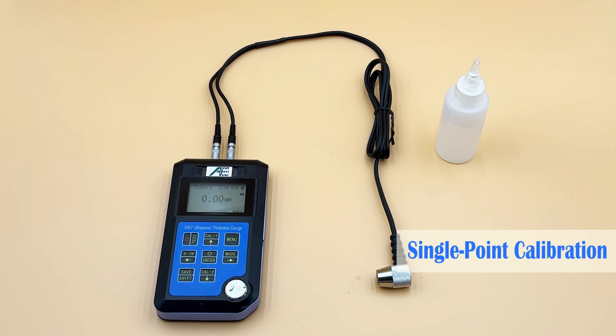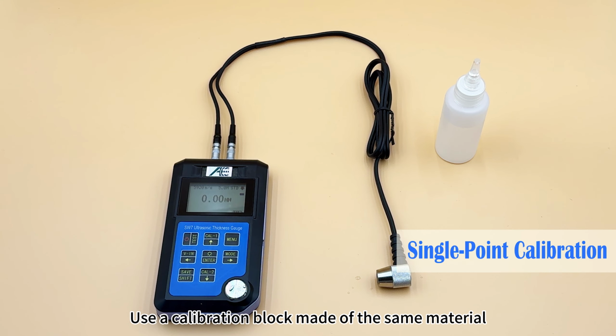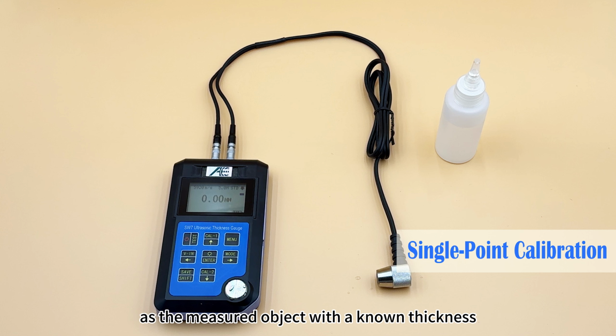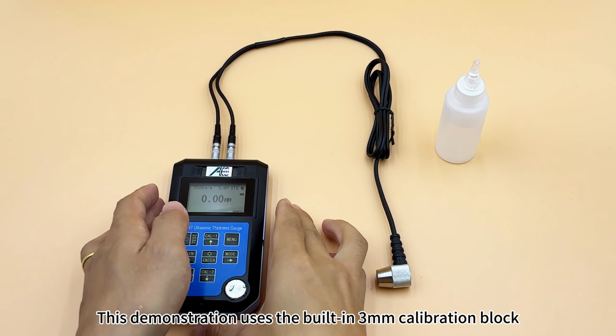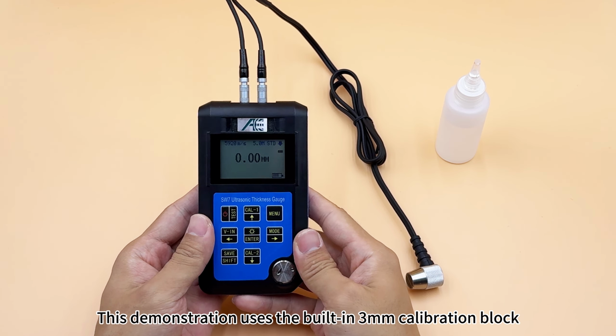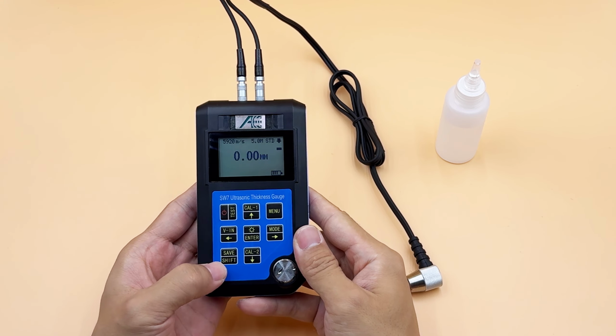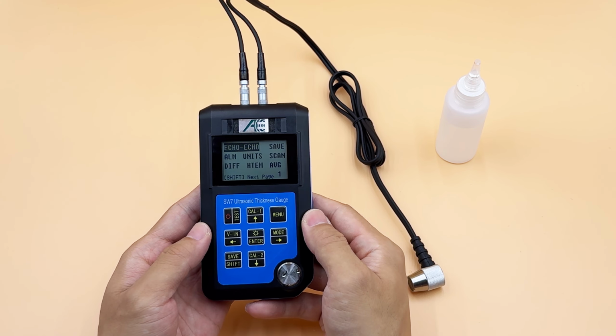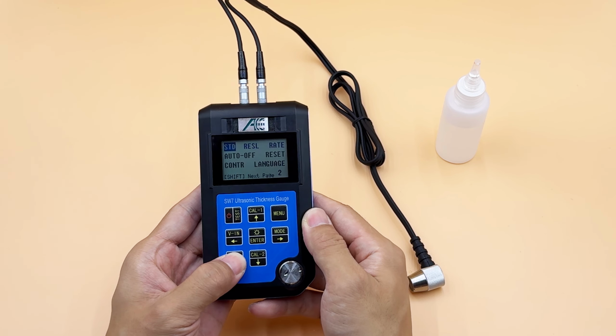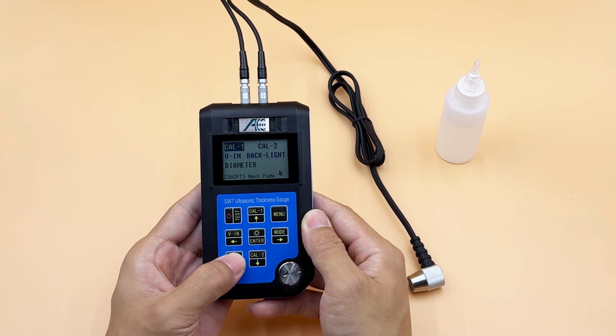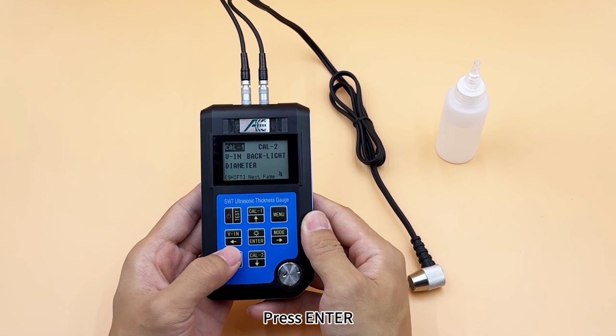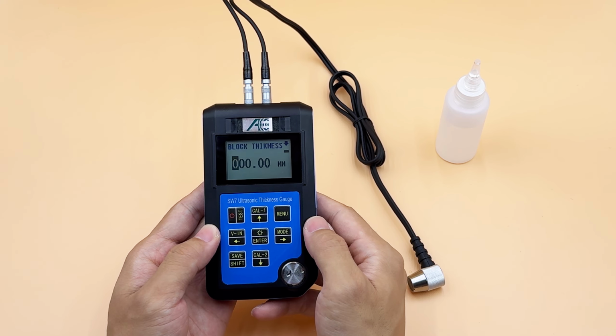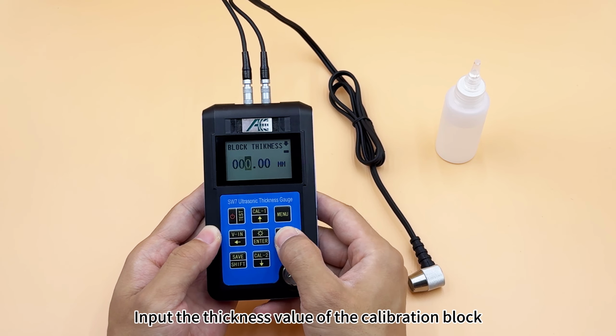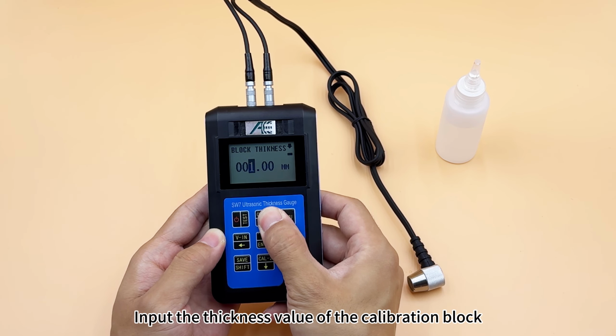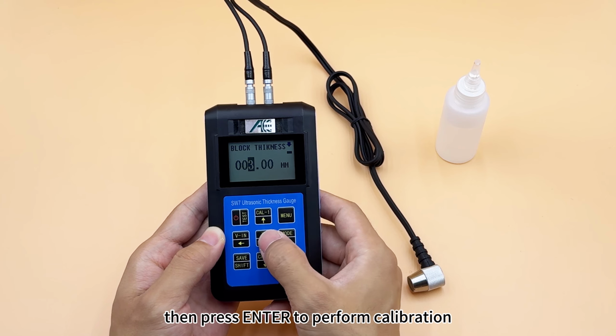Single point calibration. Use a calibration block made of the same material as the measured object with a known thickness to calibrate the device. This demonstration uses the built-in 3 mm calibration block for single-point calibration. Press menu and shift key. Select Cal 1, press enter. Input the thickness value of the calibration block, then press enter to perform calibration.